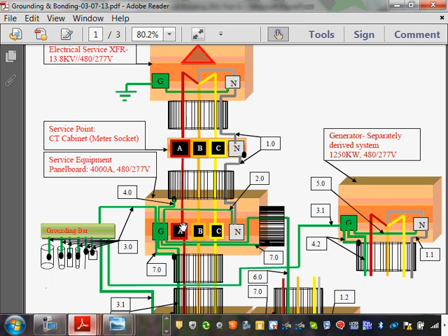If you are at your house, that bonding would be a little tiny bonding bushing that you put right here, and you tie it from here to the ground. Done. If you have a threaded hub, that will act as your bonding enclosure to your switchgear or box. That's another way. Another method is bonding lock nuts. But if you're coming into an open switchgear, you're not tying anything metal to metal here. The conduits are sitting inside the bottom of the switchgear, so you have no option of bonding lock nuts or a bonding wedge, as they call it. So there are multiple options to do this one.